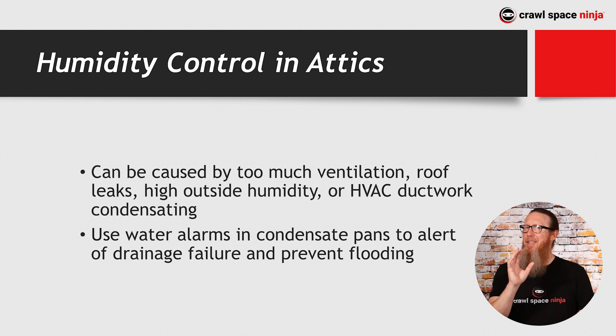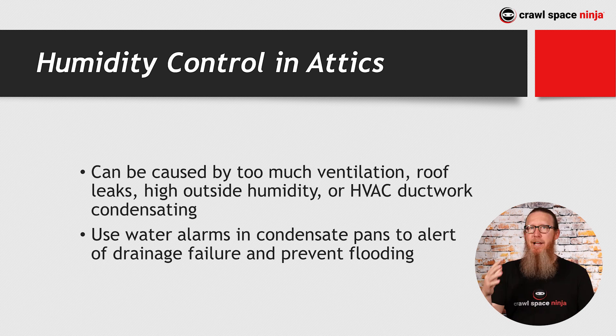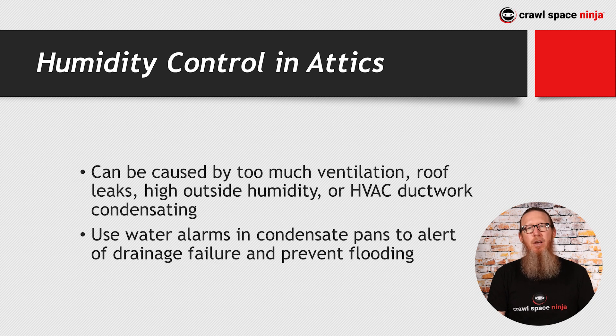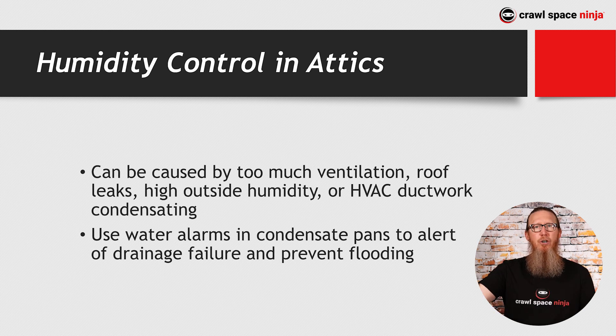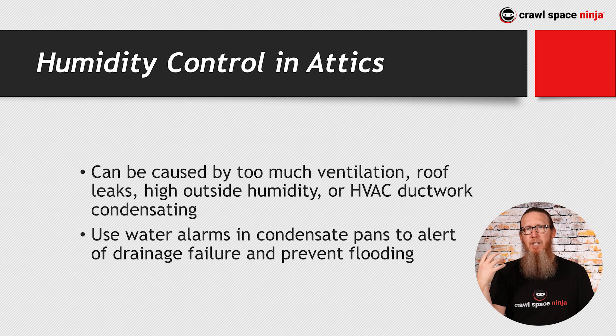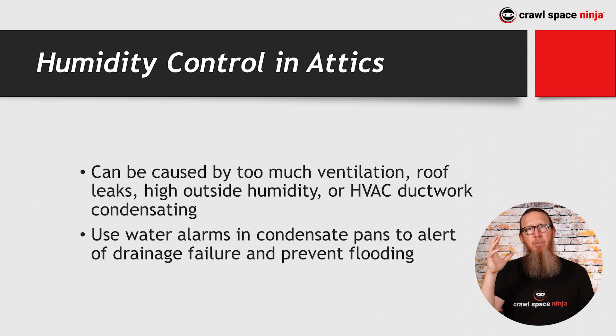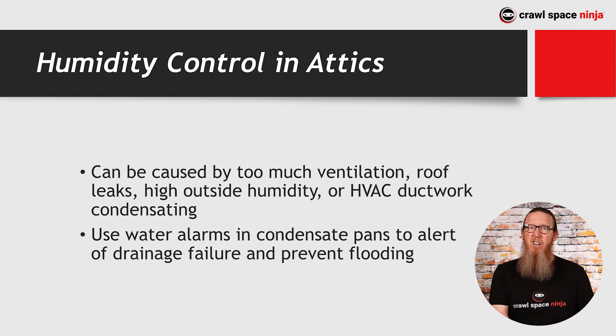Humid attics don't happen very often because most of the time an attic is pretty dry, unless you have a roof leak, flashing problems, or moisture coming in through the siding. But we have installed dehumidifiers in attics where you have a really hot humid outside environment with too much ventilation and HVAC ductwork up there. Poorly insulated or leaking ducts allow hot humid air to enter the attic, causing condensation around the ductwork, which then drips onto your drywall or ceiling and creates mold issues underneath blown-in insulation.